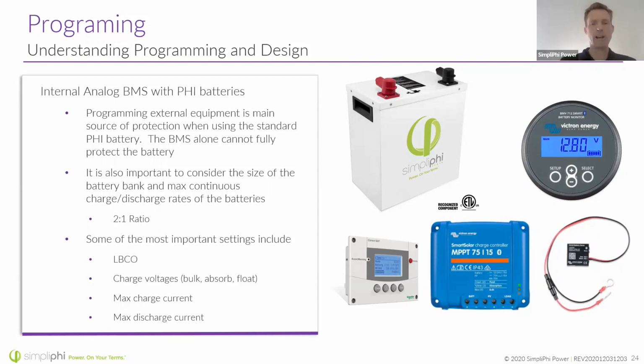Lead acid batteries had a high self-discharge rate, and so typically those batteries would be floated, right? If you leave your car for a month, the battery very well might be fully depleted when you go to start your car. Well, lithium batteries, LFP batteries, have a very low self-discharge rate, on the order of 1% if you let it sit for a month. So floating is not recommended. I guess you can do it. We recommend it at 54 volts if you're going to do it at all, and I would only do that if you have a free source of energy, such as a renewable, like wind or solar, that's providing it.